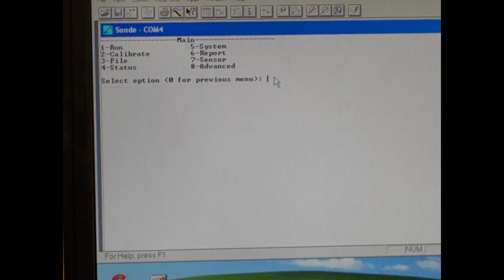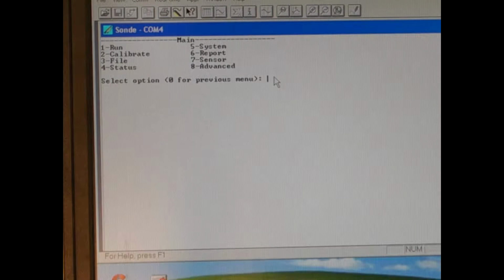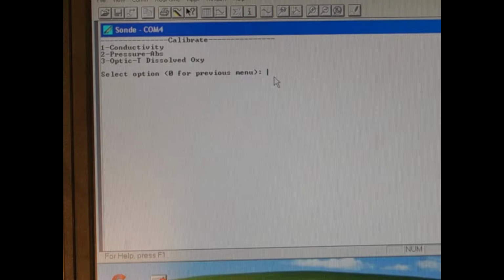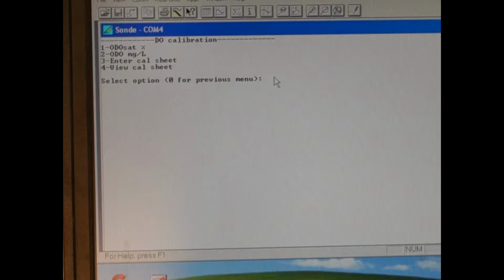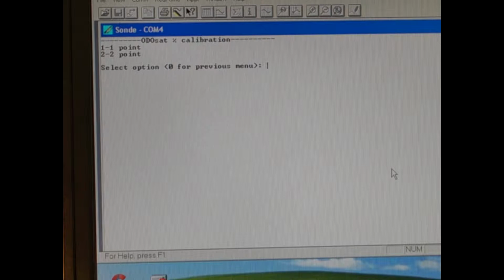All right, so we're back in our Sonde menu on the computer. So push calibrate, number 2. And now we're going to calibrate dissolved oxygen, 3. And now we're going to use percent DO saturated, which is number 1, and a 1-point calibration. The barometric pressure that the unit is reading is 761. We actually write down the pressure that we listed before on the sheet, which is 760.9. Push enter.